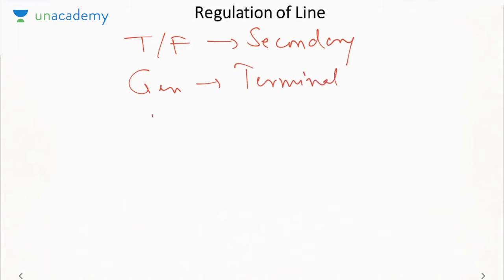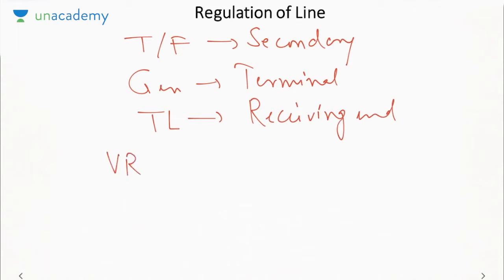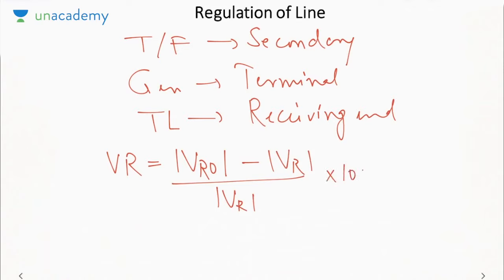For a transmission line the output is at the receiving end, so we will take it across the receiving end. So voltage regulation will be written as mod VR0, that is the receiving end voltage at no load, minus mod VR, the receiving end voltage under full load, divided by mod VR, into 100%. So remember this terminology: mod VR0 is the receiving end voltage under no load condition.